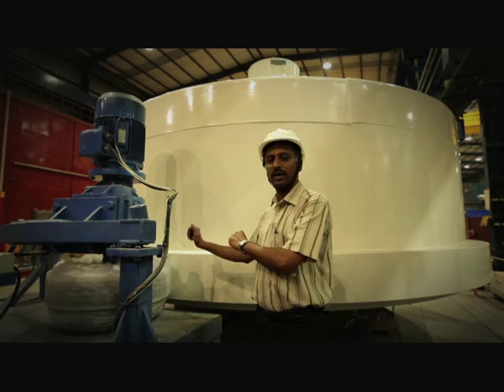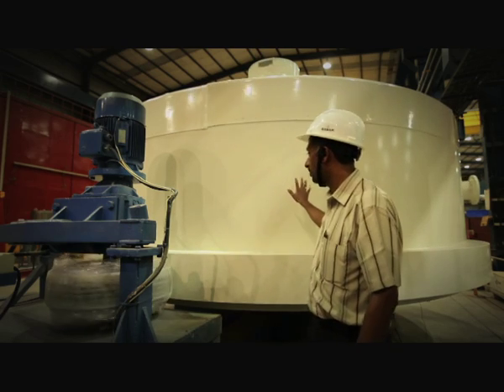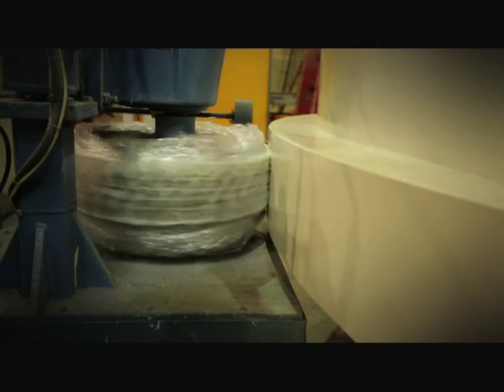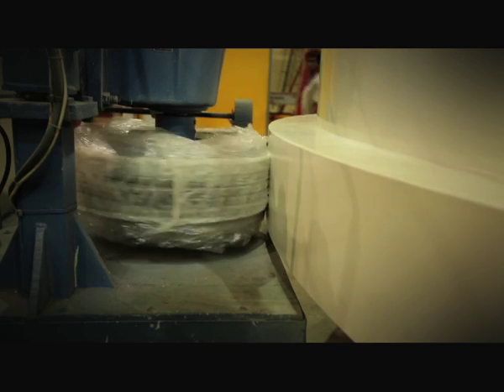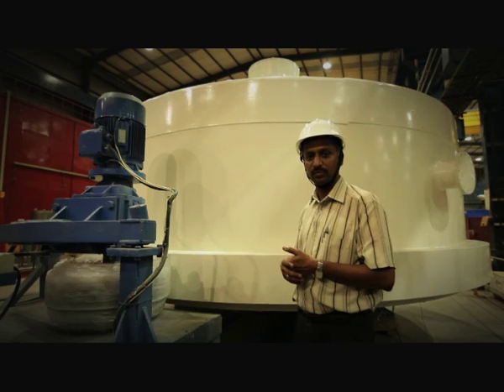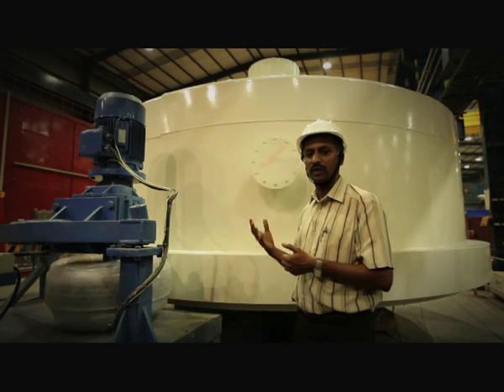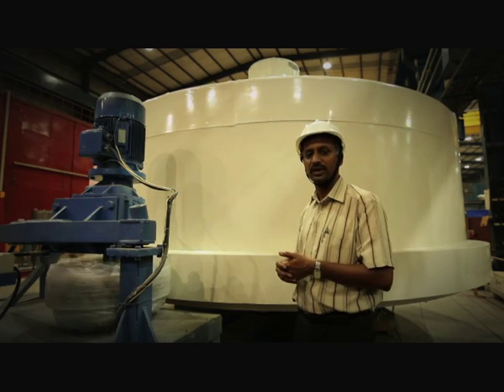This is the no load test rig. This is to check the performance of the generator. The advantage of this machine is that it's fully automated. It can be operated by a single person. There is a time reduction: earlier it took 2 hours, now we can complete the test in 15 minutes.